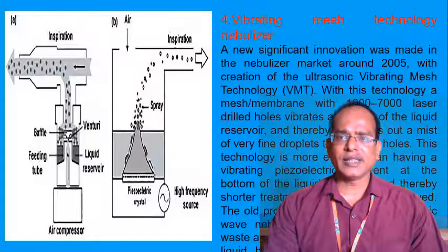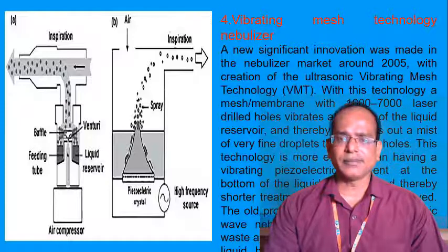So fourth one is the vibrating mesh technology nebulizer. Here the same thing, the aerosol is created with the help of a high frequency signal given at the bottom of the chamber. A new significant innovation was made in the nebulizer market around 2005 with the creation of ultrasonic vibrating mesh technology, called VMT.